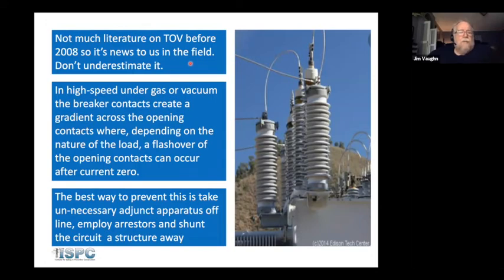Now remember, this is all occurring at the speed of light, and it only takes that fraction of a second for the flashover to occur and toast you well if you're inside of that space. So the best way to prevent this, and I'll show you a study in a minute that's recommended by the IEEE, for some of the things that your utility can do or should be doing if you're working on energized transmission circuits. So the best way to prevent this is if you have adjunct apparatus like capacitor banks or reactor banks that are on the line, open them, take them offline while you're doing your work. This ensures that something is not going to cause them to inadvertently or unexpectedly open because of a relay scheme that occurs someplace, and that limits the opportunities for unexpected openings of the circuit.